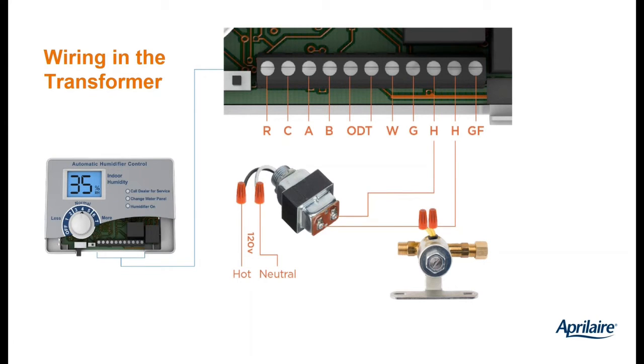The humidistat outputs a dry contact, and all of our evaporative humidifiers require 24 volts to run. So you'd use the field supplied transformer, the 24 volt 10 VA transformer, to supply the 24 volts. So you can just wire that 24 volt transformer into the 120 volts anywhere inside the HVAC system before it goes into the circuit board or before it goes into the blower, of course.